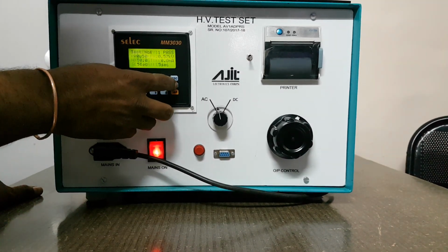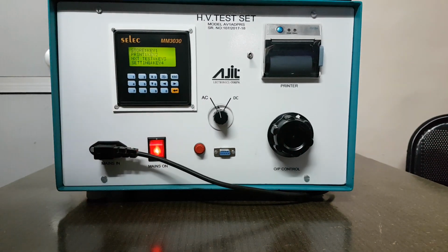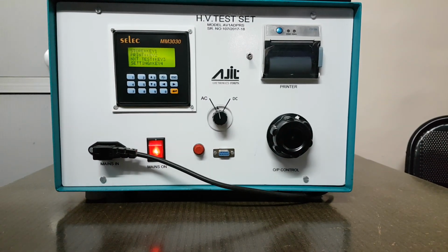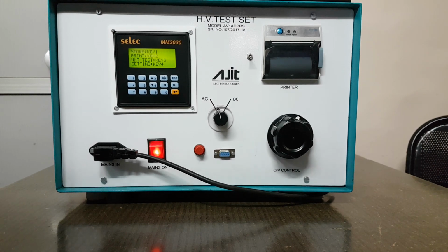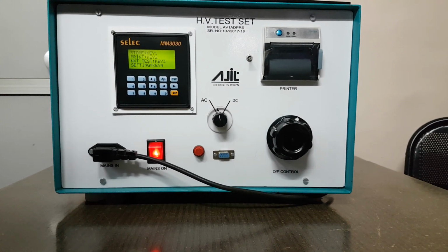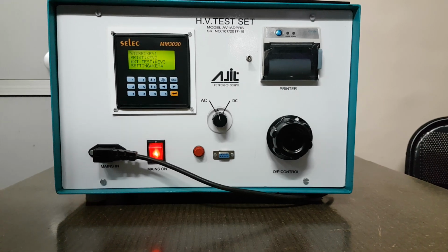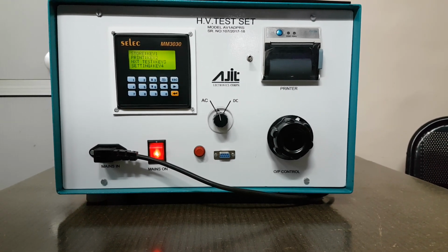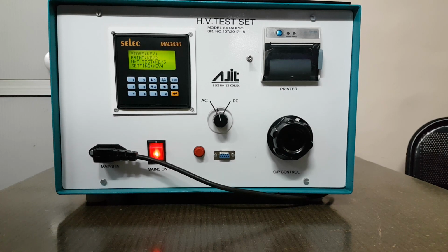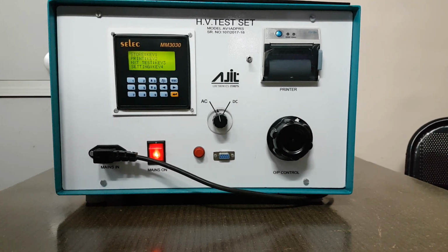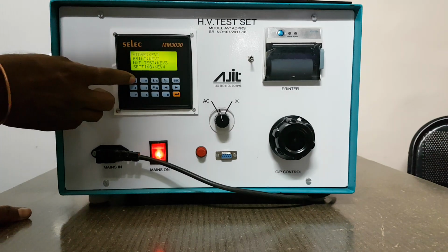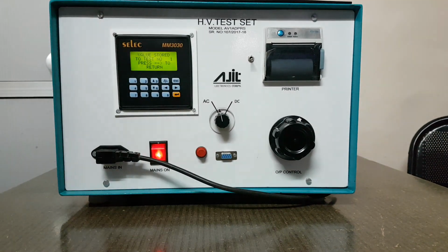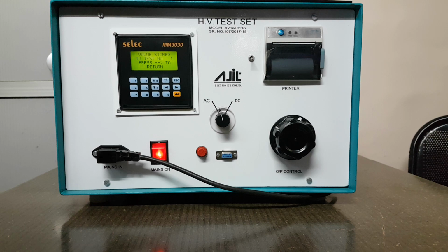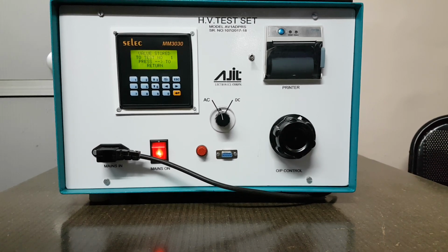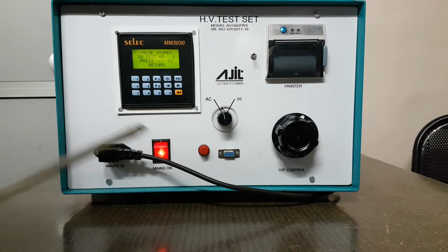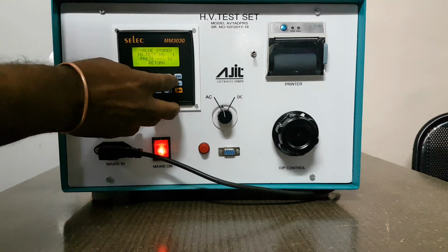Now the next page. The next page says press 1 to store the values, press 2 to take a print, press 3 for the next test and press 4 for the next setting. Let's press 1. Now the instrument says the value is stored to test number 1. Press arrow to return.